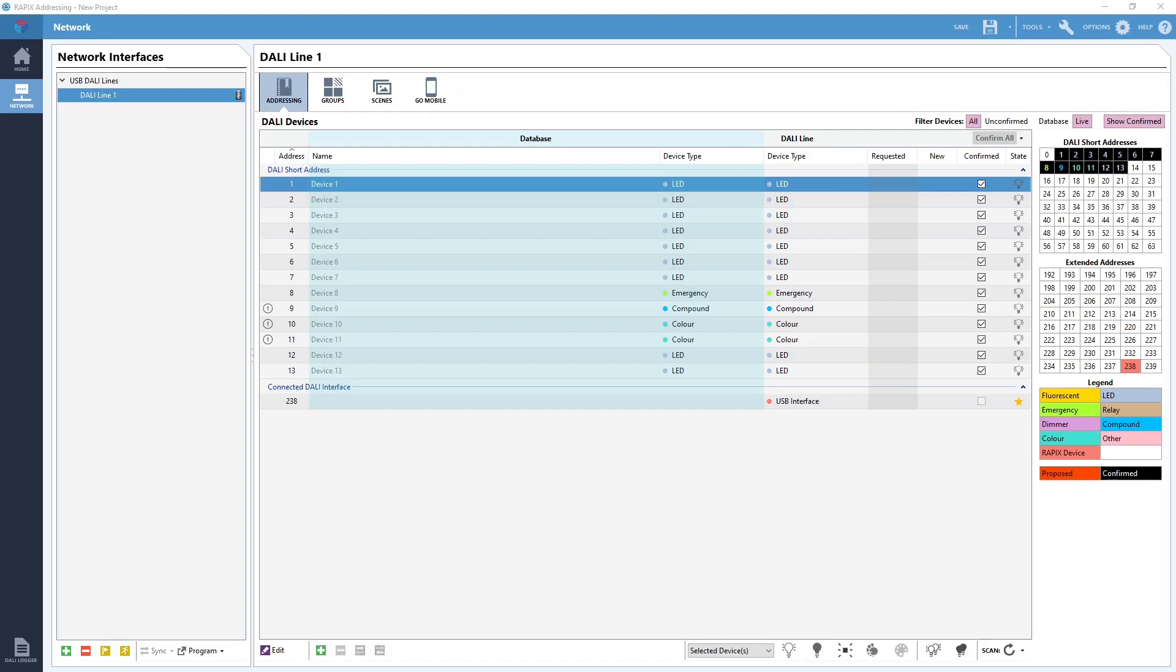The purpose of a DALI group is to allow a single DALI command to control multiple DALI devices at the same time. We could command a DALI group to turn on or off, dim up and down, or fade to a specific level, and all the DALI devices that are members of that group will follow the command.